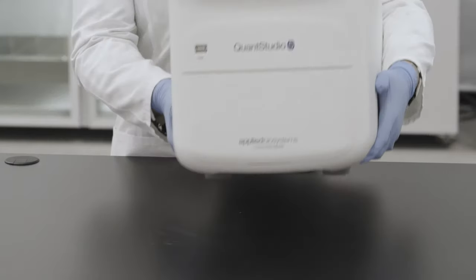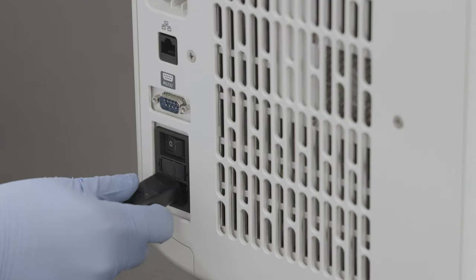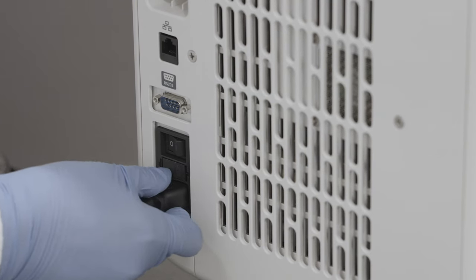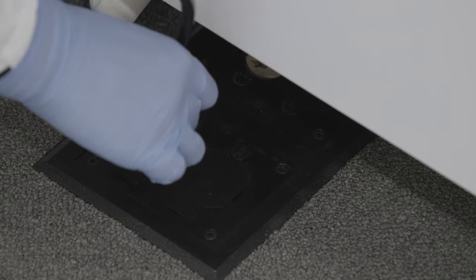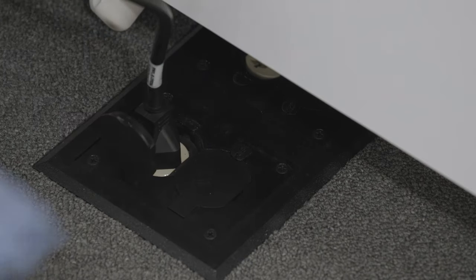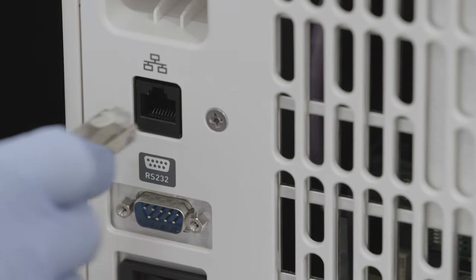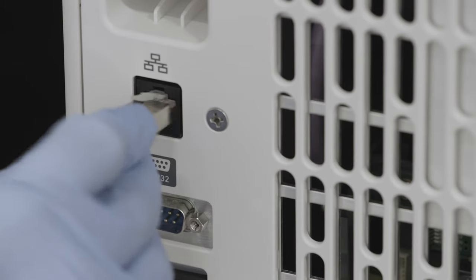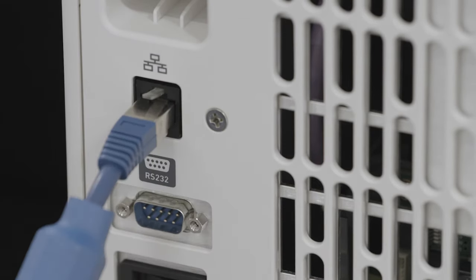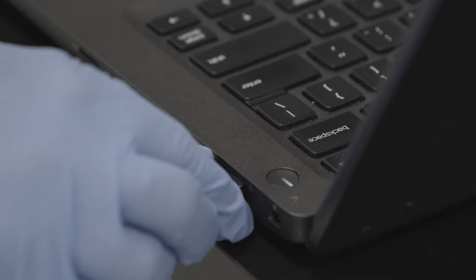Place the instrument on the bench and plug the power cable into the power port on the back panel of the instrument. Then plug the cable into an electrical outlet. Connect one end of an Ethernet cable to the Ethernet port on the back panel of the system and the other end to a computer.